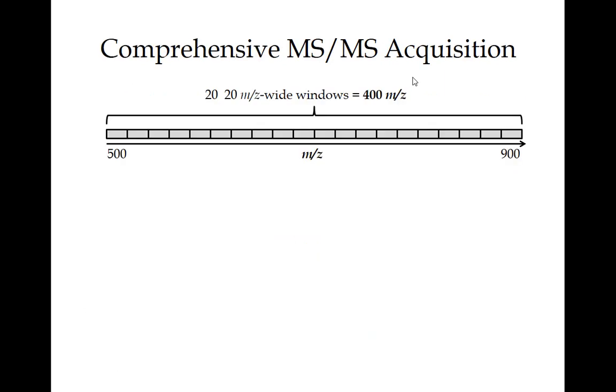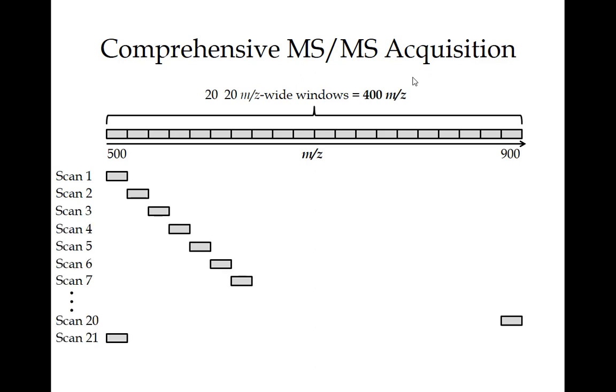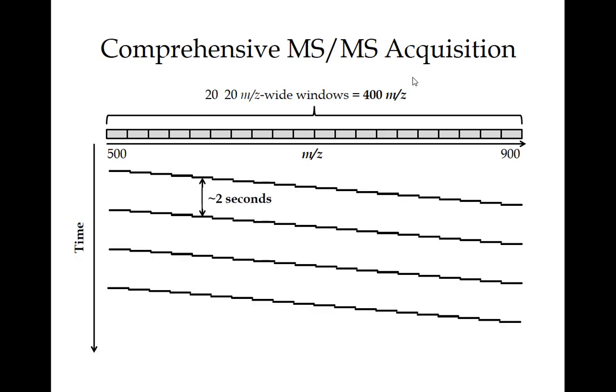This schematic shows traditional DIA methods. The first scan is an MS/MS scan measuring 500 to 520 m/z — isolating all precursors in that window and fragmenting them. The next scan jumps ahead by 20 m/z. These adjacent scans isolate and acquire, and the cycle continues until scan 20, then goes back. In this way, the entire range is covered. We try to make this entire process take about two seconds on our systems.